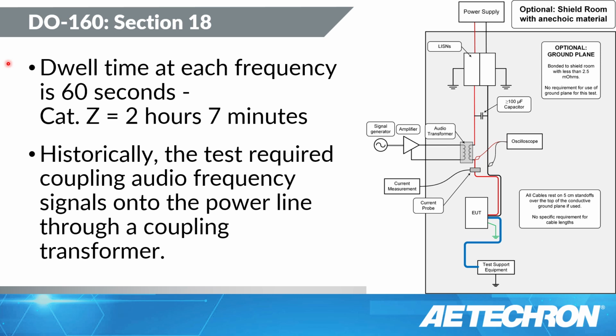Now, historically, this test has been done by using a coupling transformer. AE Techron has a T2000. It's a wonderful transformer, works very, very well. You route your signal source, this is a 3110, let's say, into a 7234 amplifier, goes through the transformer, and that couples the voltage onto the power line.